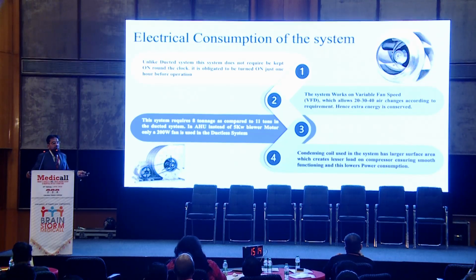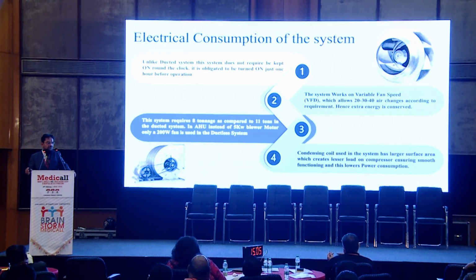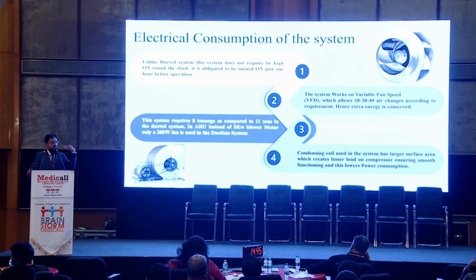Then the condensing coil, the cooling coil which we are using in my system, has a higher fin area, meaning more copper pipe is given for making the cooling coil. Normally most companies, big companies also, take around 3.5 square feet per ton. Instead of that, we are giving 4.5. So if the cooling area is bigger and the ambient temperature is high, you will not find any load on the compressors. Apart from that, we are using blue fin cooling coil, so the life of the cooling coil will be not less than 15 to 20 years.